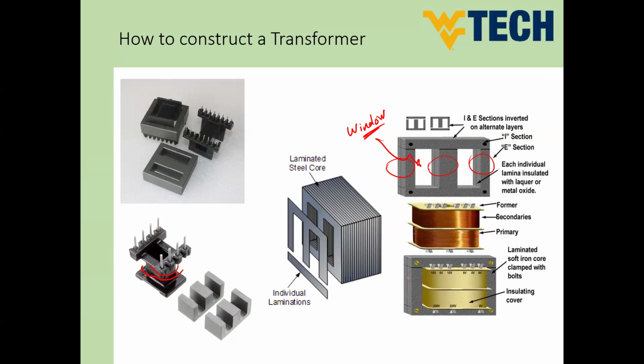avoid any air between these sheets, because if you have some air inside, this would make a very huge noise, and we can actually hear that in some transformers. This means that, because of the vibration, the transformer can make some air gap between the laminations. So it needs to be tighter in order to reduce or avoid such noise in transformers. Okay. After doing that, guys, on this core, we have to add insulation on the cores like that. So we have an insulating cover here.